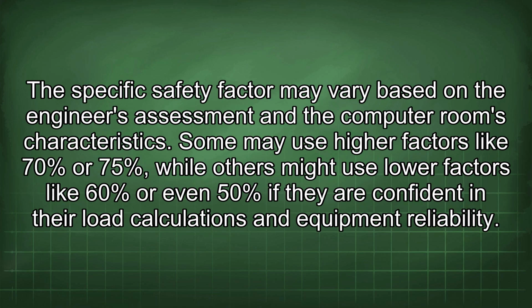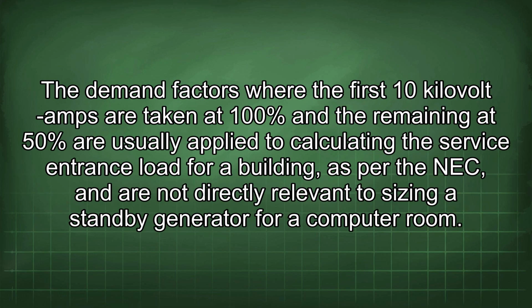The specific safety factor may vary based on the engineer's assessment and the computer room's characteristics. Some may use higher factors like 70% or 75%, while others might use lower factors like 60% or even 50% if they are confident in their load calculations and equipment reliability. The demand factors where the first 10 kVA are taken at 100% and the remaining at 50% are usually applied to calculating the service entrance load for a building, as per the NEC, and are not directly relevant to sizing a standby generator for a computer room.